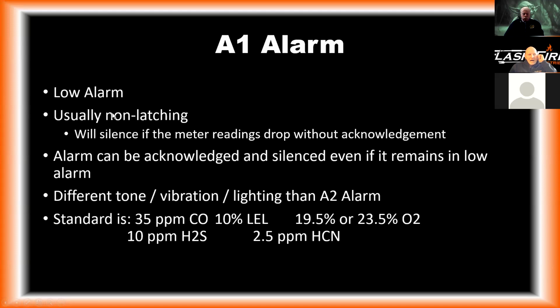The low alarm is usually non-latching, and what that means is the meter is going to silence without acknowledgement. So if my CO low alarm is 35 parts per million, I go up to 40 parts per million, it alarms, and then I walk outside, I come back and it goes down to 0, it's going to stop alarming. I never acknowledged it, so there's no guarantee that I even knew that it went off. The alarms can be silenced. So if it stays in low alarm, it remains at 40 parts per million, which is above my low alarm but below my high alarm, I can silence the meter and continue operating.